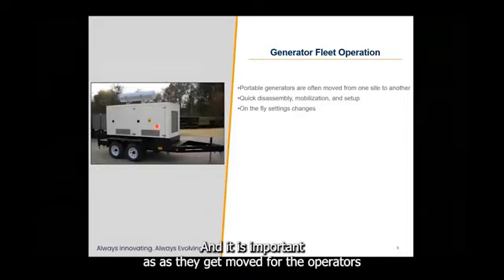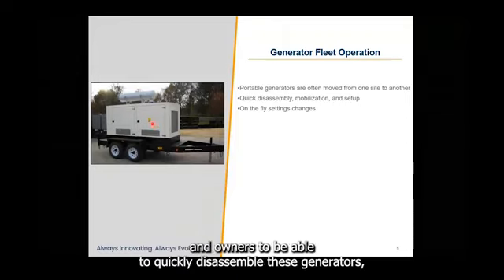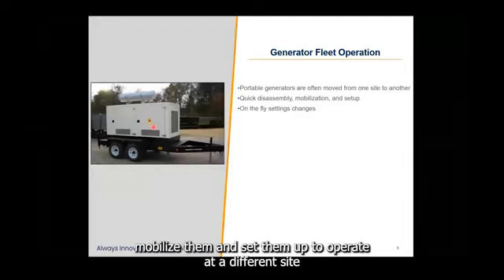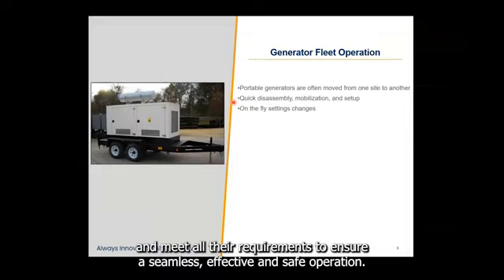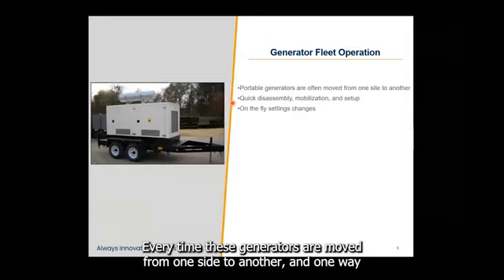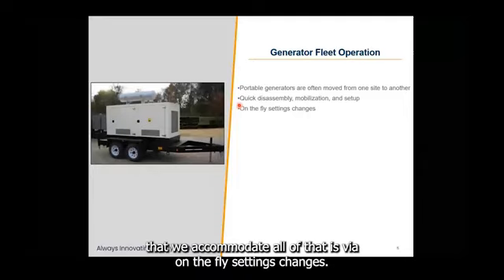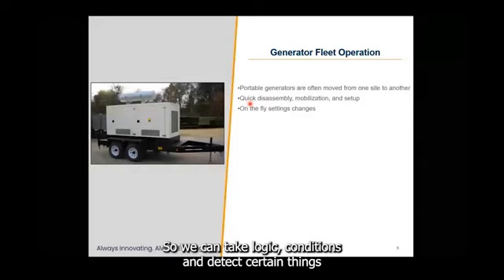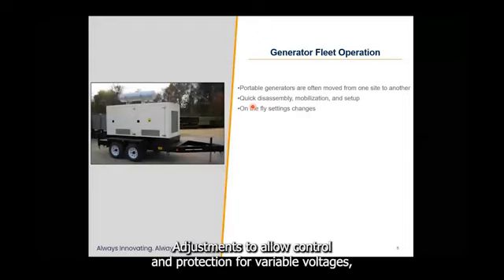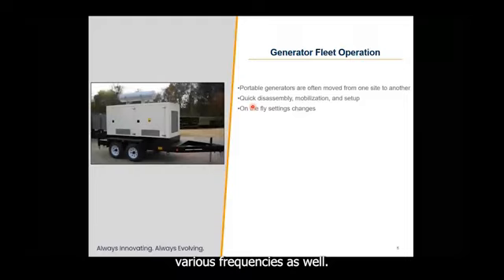And it is important as they get moved for the operators and owners to be able to quickly disassemble these generators, mobilize them, and set them up to operate at a different site and meet all the requirements to ensure a seamless, effective, and safe operation every time these generators are moved from one site to another. And one way that we accommodate all of that is via on-the-fly settings changes. So we can take logic conditions and detect certain things about the generator's operation to make on-the-fly settings adjustments to allow control and protection for variable voltages, various frequencies as well.